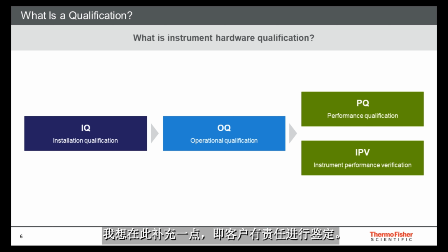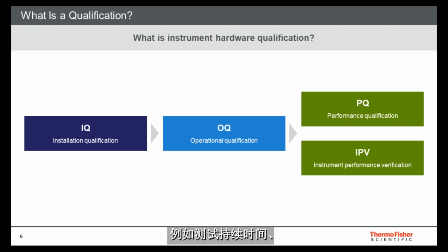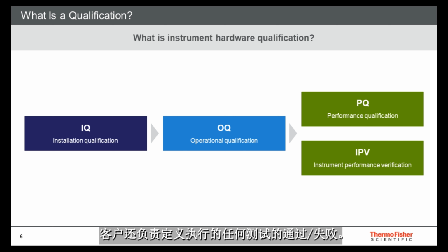Thanks, Randall. One thing that I'd like to add here is that the qualification is the customer's responsibility. And by that, I mean that the customer should have pre-approved documents to capture the tasks being completed during the qualification. With cold storage testing, we can provide the temperature mapping to fulfill the requirement of a qualification document. The customer will be responsible for the details of the tests, such as test duration, open door sample pulse simulation, and power-off testing. The customer is also responsible for defining the pass-fail of any testing that is performed.